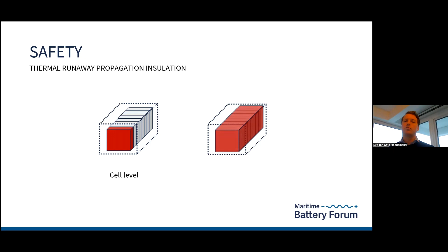The second level of safety that battery manufacturers can choose is at module level. So if one of the modules goes into thermal runaway, it can spread to all the cells inside that module, but it will not propagate from module to module. This is module level thermal runaway propagation isolation.